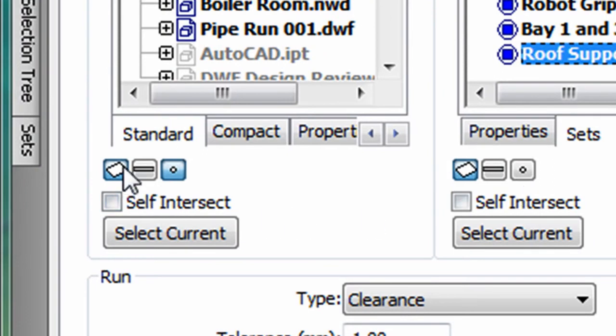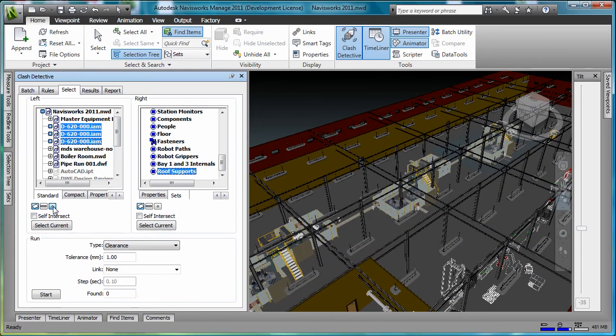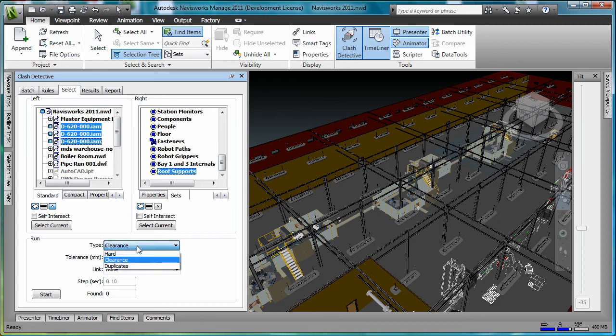Navisworks can analyze the interference between the selection sets based on surfaces, lines, and points. We need to make sure we set both of these sets for surface analysis. I also want to make sure of the interference type. In this case, we'll be checking for hard interferences.